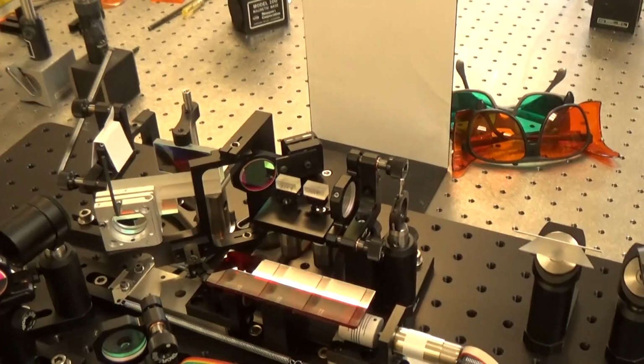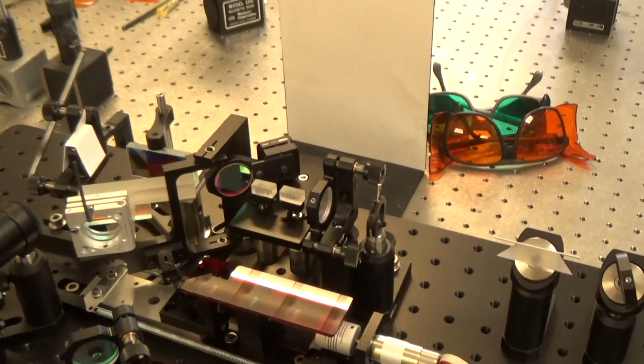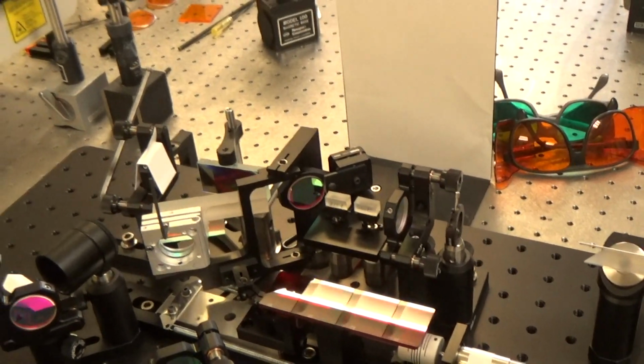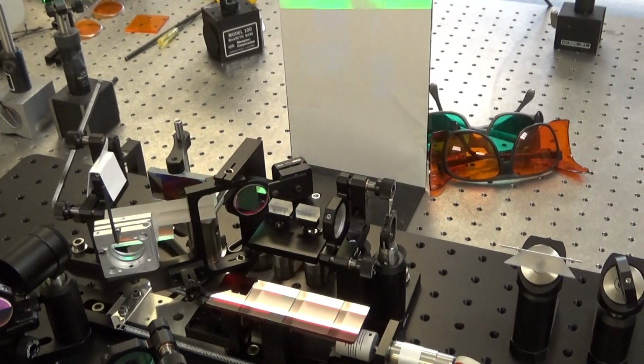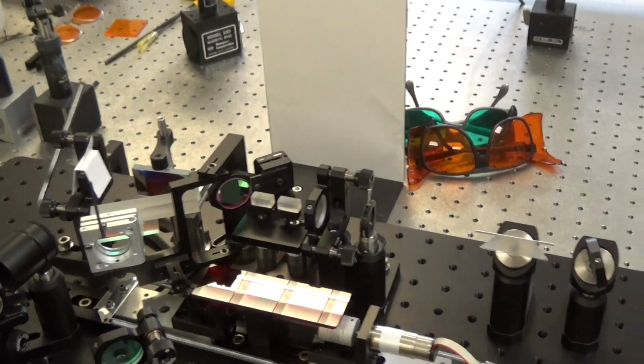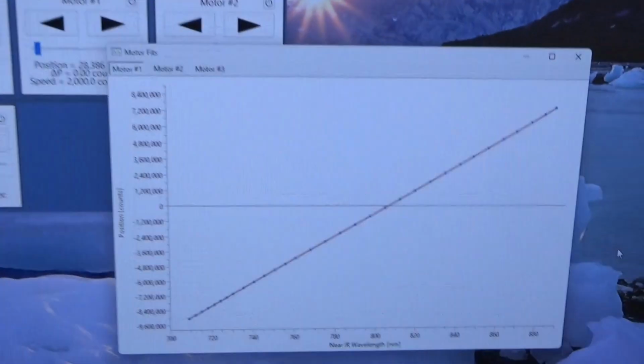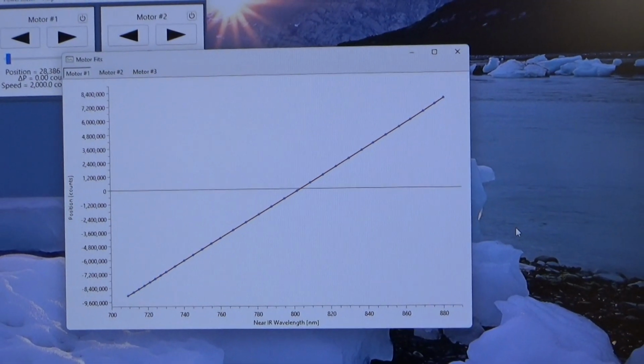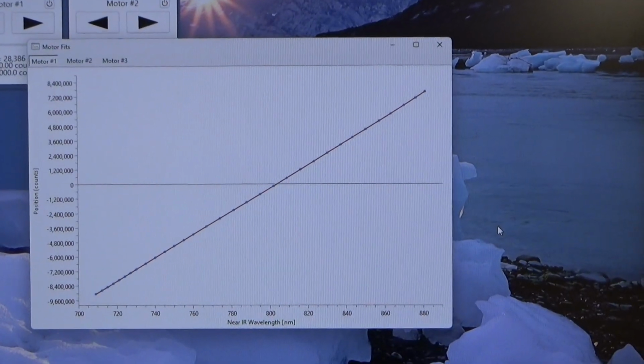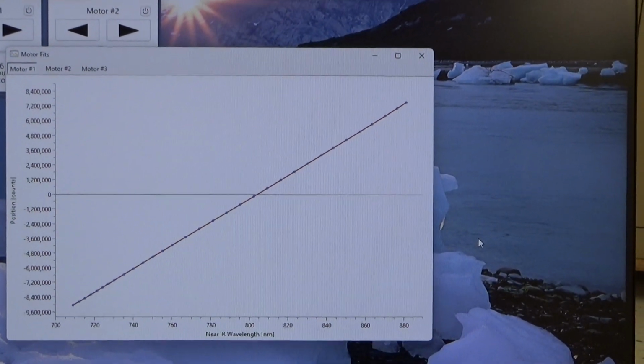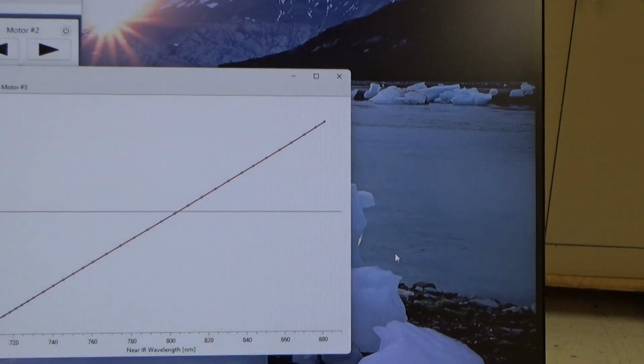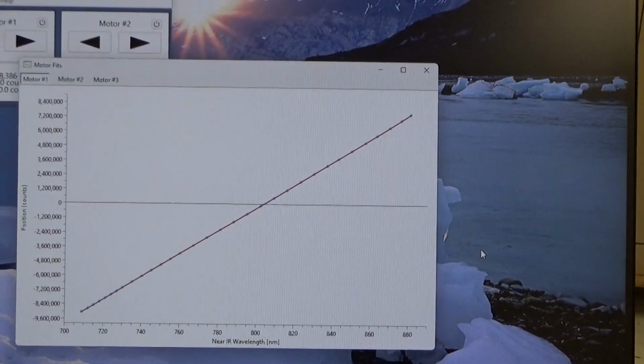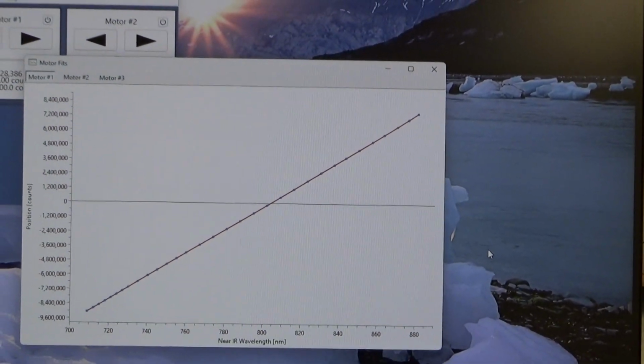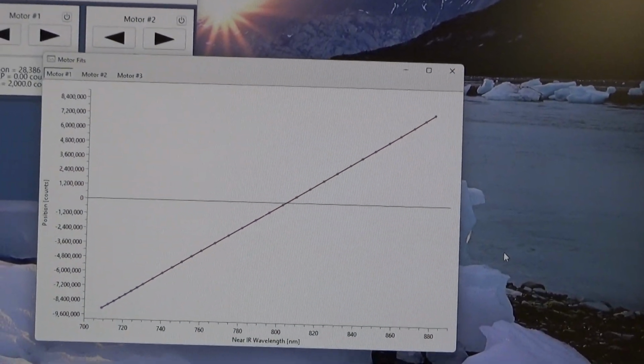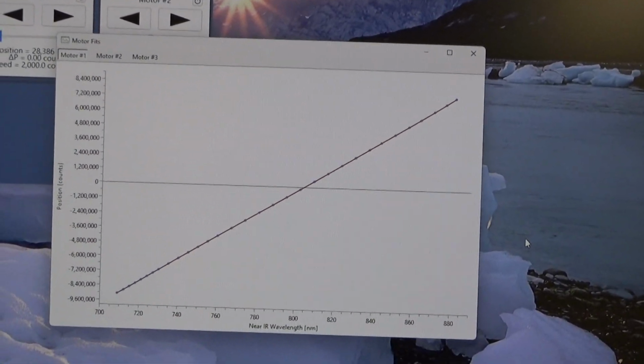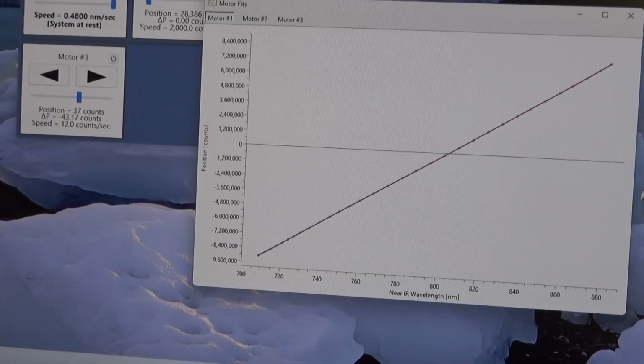I've got the oscillator up and running at 803.5 nanometers. The next step for calibrating the oscillator, I like to go down to the beginning of the tuning range at 710, and then take data points every 5 to 7 nanometers all the way out to the end of tuning, which is at around 880 nanometers.